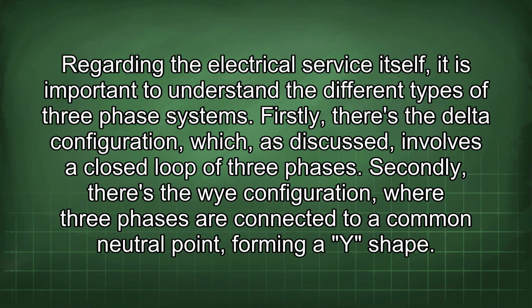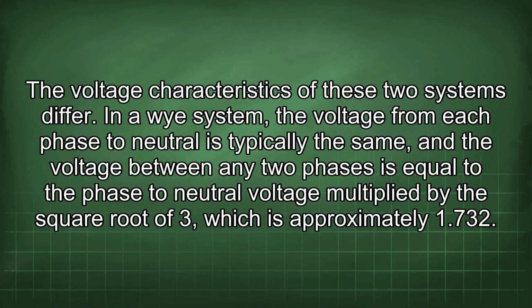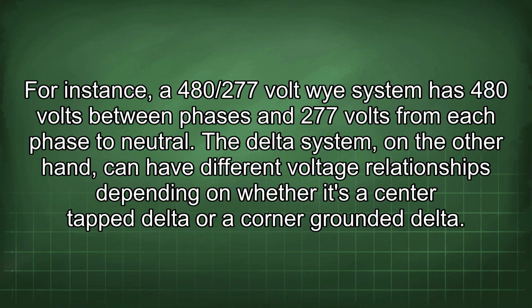Regarding the electrical service itself, it is important to understand the different types of three-phase systems. Firstly, there's the delta configuration, which, as discussed, involves a closed loop of three phases. Secondly, there's the Y configuration, where three phases are connected to a common neutral point, forming a Y shape. The voltage characteristics of these two systems differ. In a Y system, the voltage from each phase to neutral is typically the same, and the voltage between any two phases is equal to the phase-to-neutral voltage multiplied by the square root of 3, which is approximately 1.732. For instance, a 480/277 volt Y system has 480 volts between phases and 277 volts from each phase to neutral.